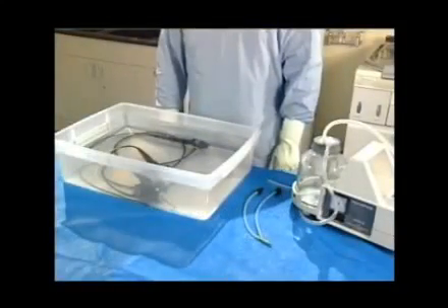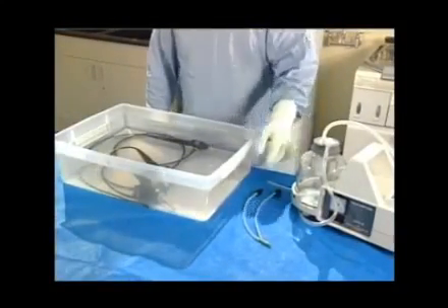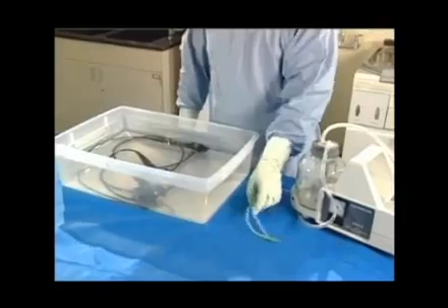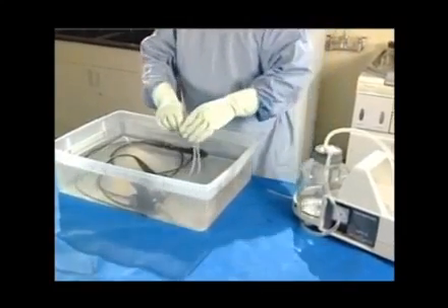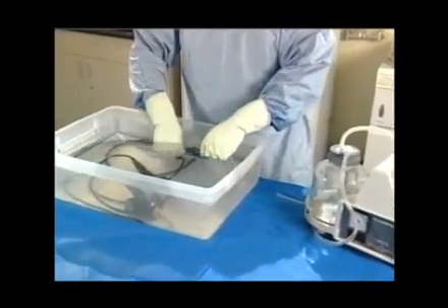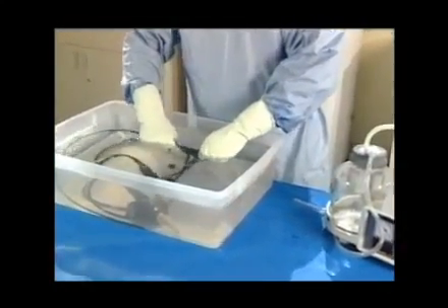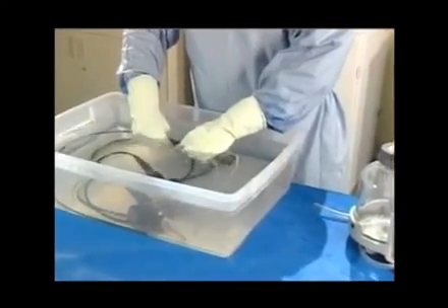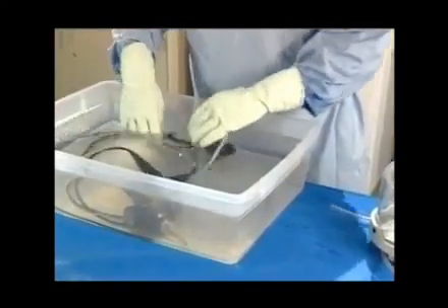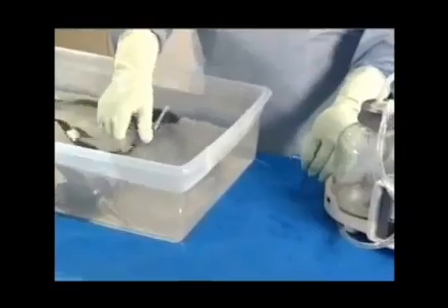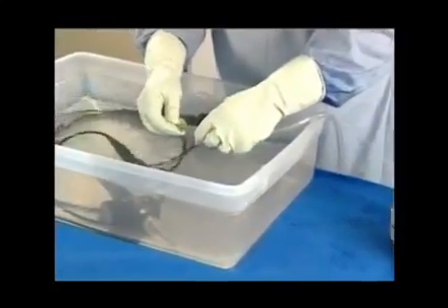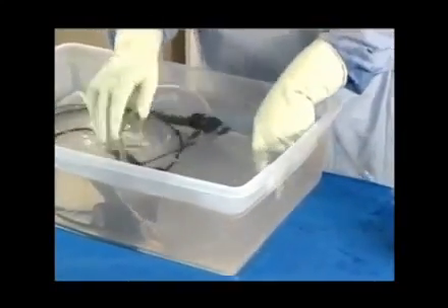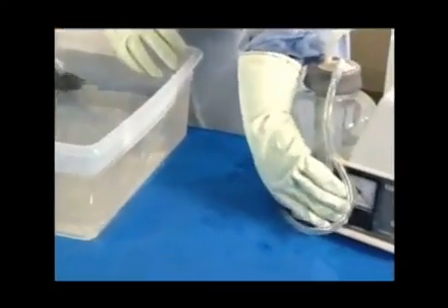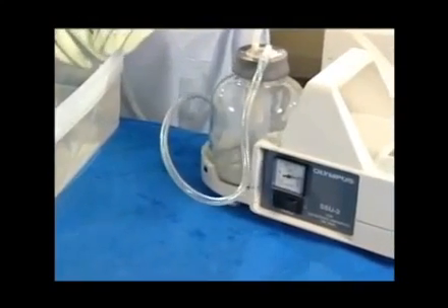Now that the channels have been brushed, the next step is to flush the channels with detergent solution to remove any remaining debris. Attach the suction cleaning adapter to the bronchoscope. Attach the adapter to a source of suction. Immerse the distal tip of the bronchoscope in detergent solution and aspirate the detergent for 30 seconds.